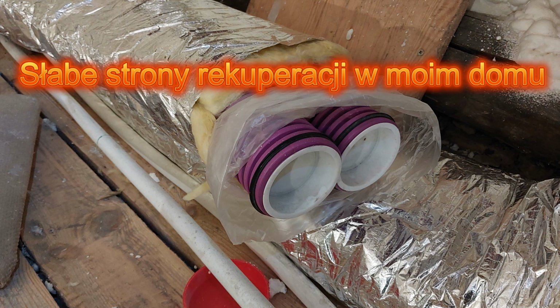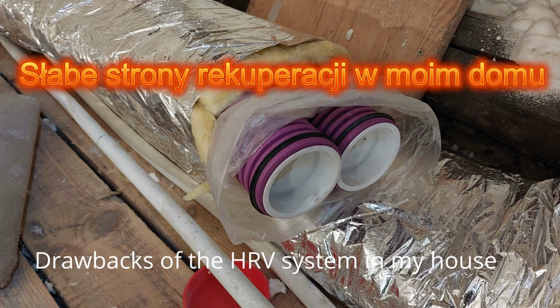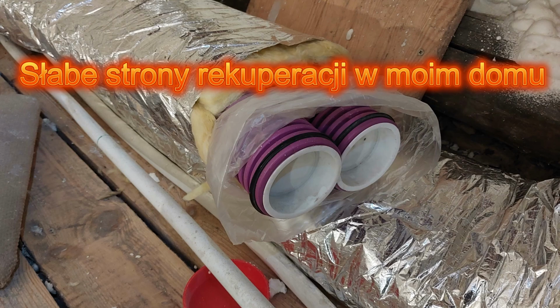Let's begin with the weak points of my heat recovery ventilation system. First, there's the complete inability to install a larger number of ventilation ducts, particularly on the very narrow wall sections. A further critical issue involves several extremely sharp bends in the ductwork, which will inevitably increase air resistance and, as a result, significantly complicate the precise regulation of the entire installation later on.